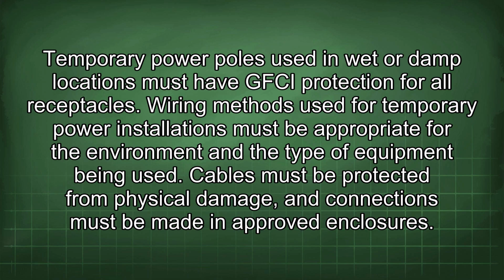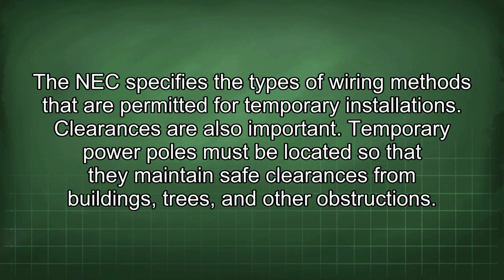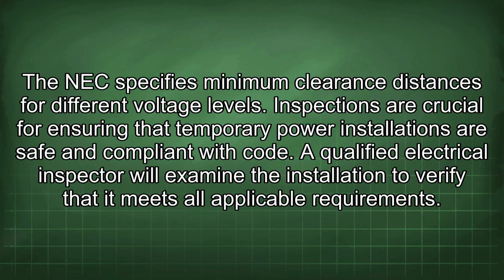Wiring methods used for temporary power installations must be appropriate for the environment and the type of equipment being used. Cables must be protected from physical damage, and connections must be made in approved enclosures. The NEC specifies the types of wiring methods that are permitted for temporary installations. Clearances are also important. Temporary power poles must be located so that they maintain safe clearances from buildings, trees, and other obstructions. The NEC specifies minimum clearance distances for different voltage levels.